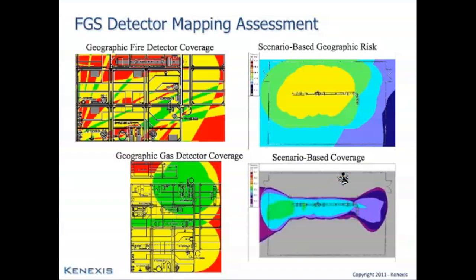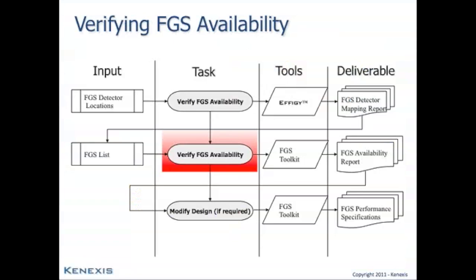Ultimately, the scenario-based coverage is going to calculate a fraction of the number of release scenarios that are detected by the fire or gas detection array. After looking at coverage, the next step is to verify the availability of the fire and gas detection and suppression system.